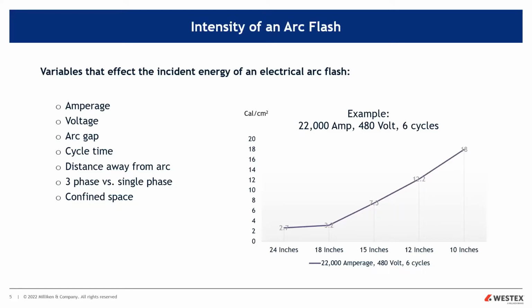And of course, when we talk about using the tables in the standard, the second table, the PPE Cat table, has notes on maximums on available fault current and maximums on clearing time, as well as minimum work distances. And that's so the incident energies do not exceed the arc ratings of the PPE for that PPE category. And of course, on the right-hand side here, I have distance. Distance is your friend, of course. The further you are away, the better. The incident energy goes off dramatically.